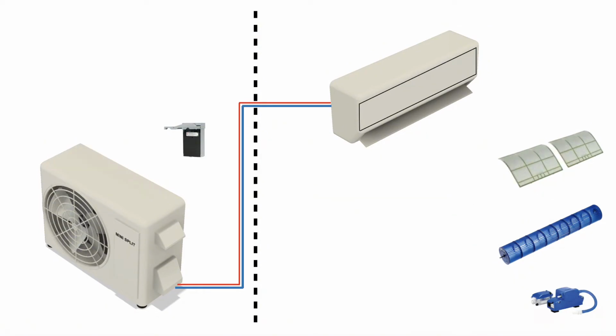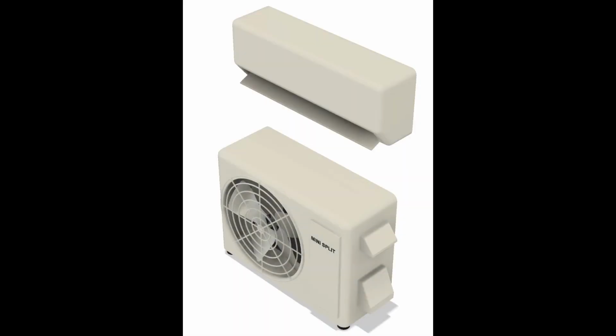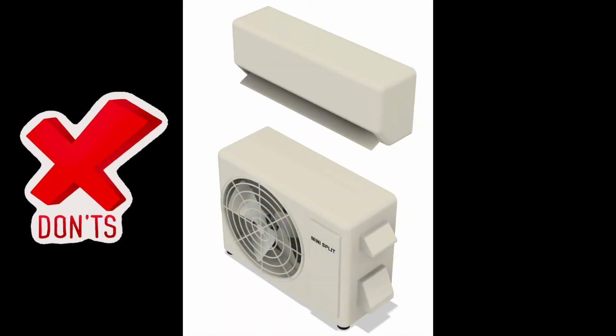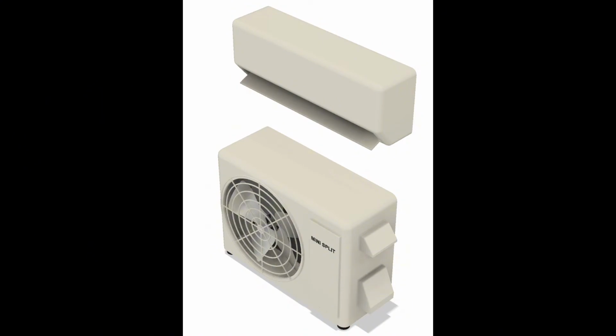And then also check the suction line temp. That suction line temp should be nice and cool. I would not recommend hooking up your manifold gauge set to a mini-split system during a preventative maintenance if you're an HVAC tech. The refrigerant charge in these mini-splits is very exact and small. You don't want to risk losing refrigerant or messing up the charge. So I would only hook up a manifold gauge set during like a troubleshooting procedure if you're trying to make a repair or a diagnosis because you have a problem, but not during preventative maintenance, in my professional opinion.